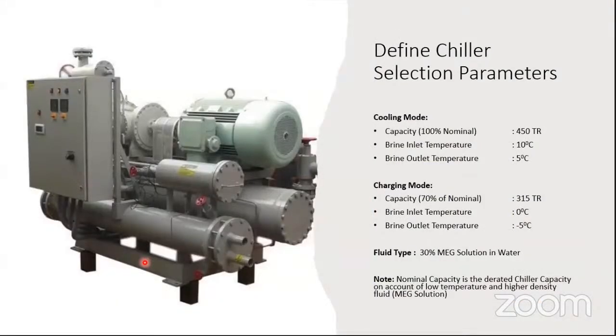So once we have designed the thermal storage system, we need to arrive at the selection parameters also, so that all these separate parts can be given to their experts. For example, once I have designed the thermal storage system and I know its supply and return performances, the inlet and outlet temperature, which of course we know will be during the cooling. I want to highlight something here. In this slide, we are defining the chiller selection parameters so that we can give it to our chiller manufacturer and tell him that this is what we need.